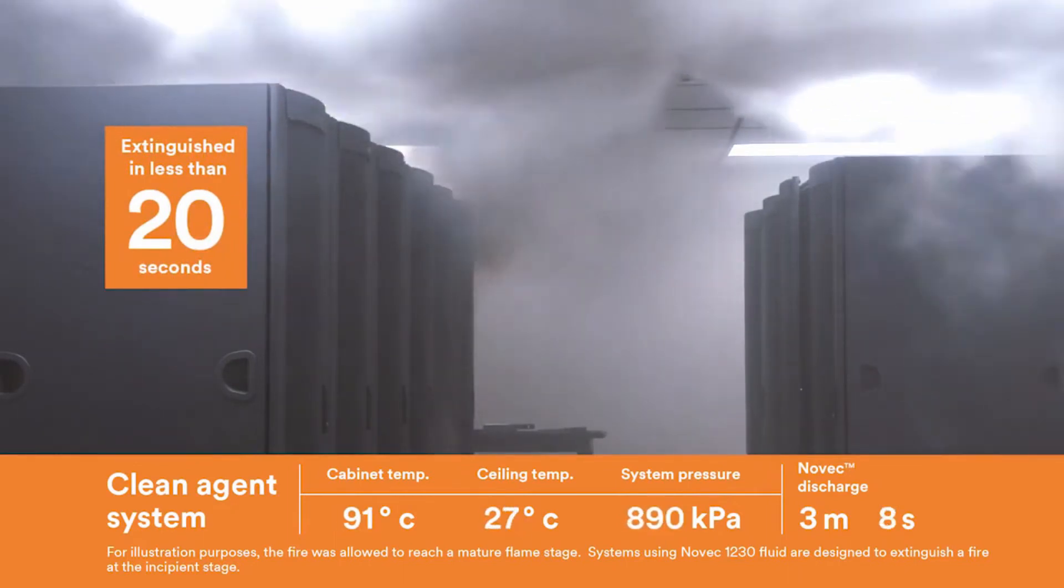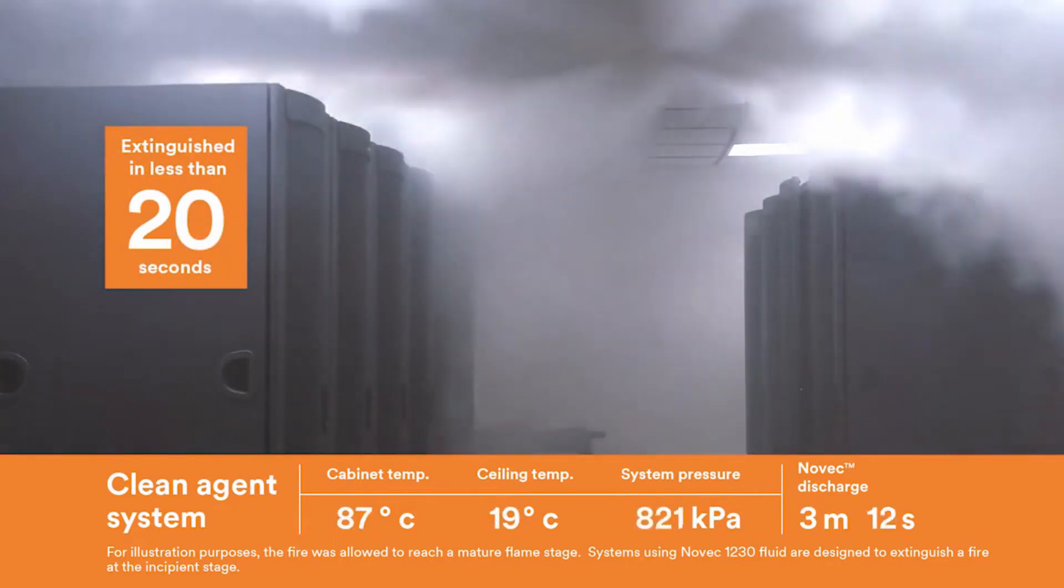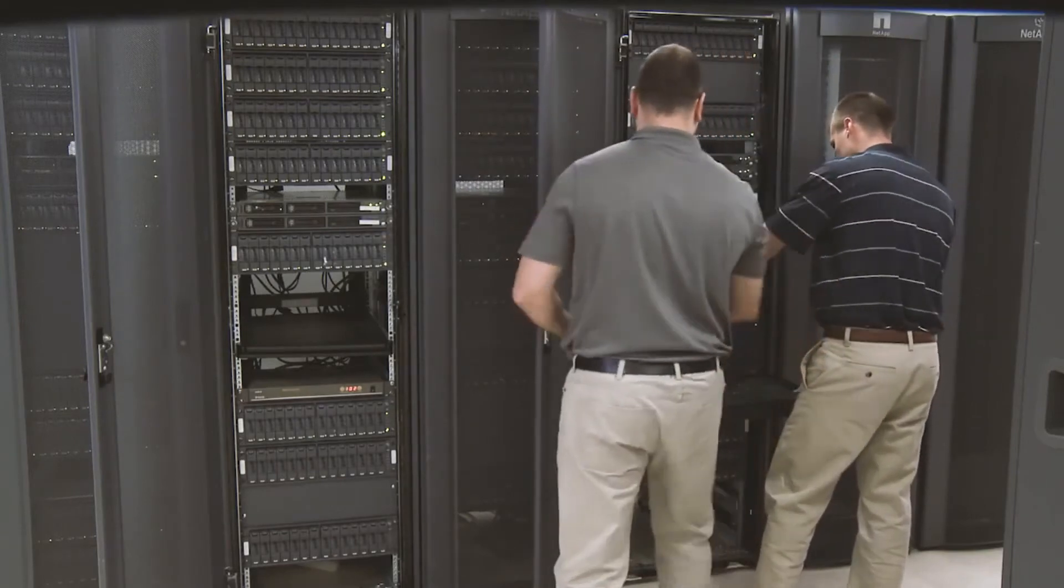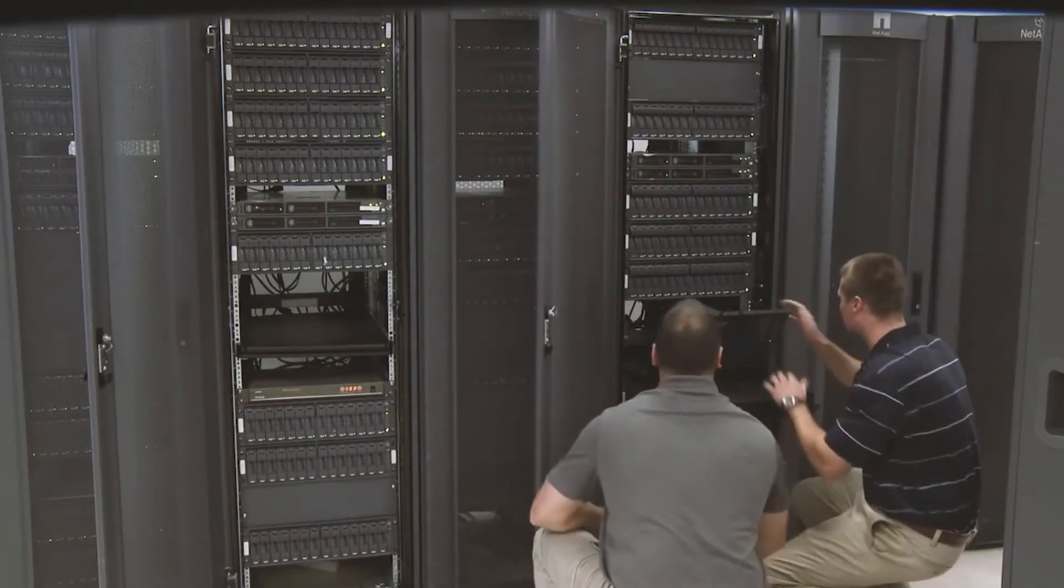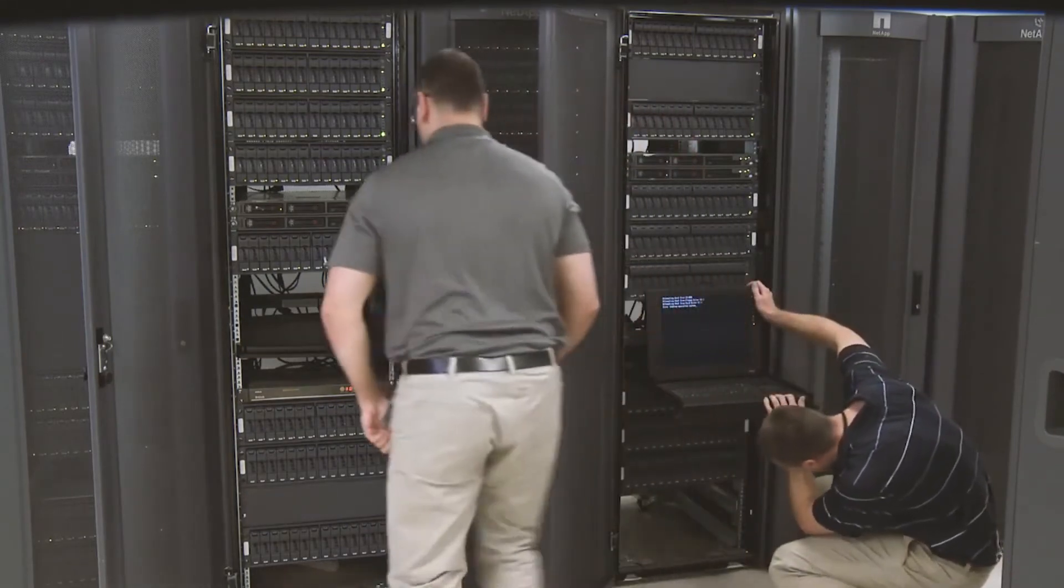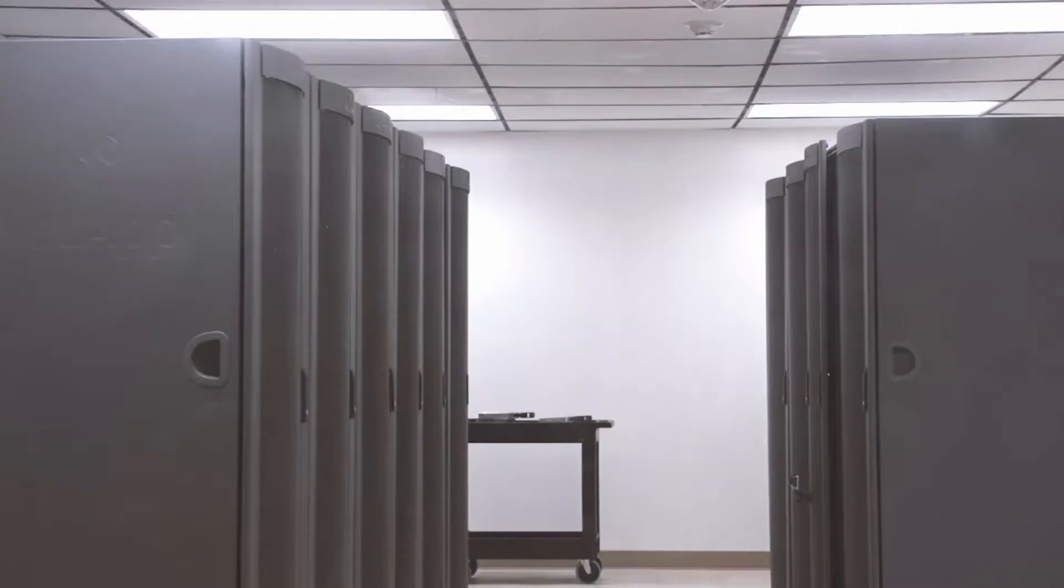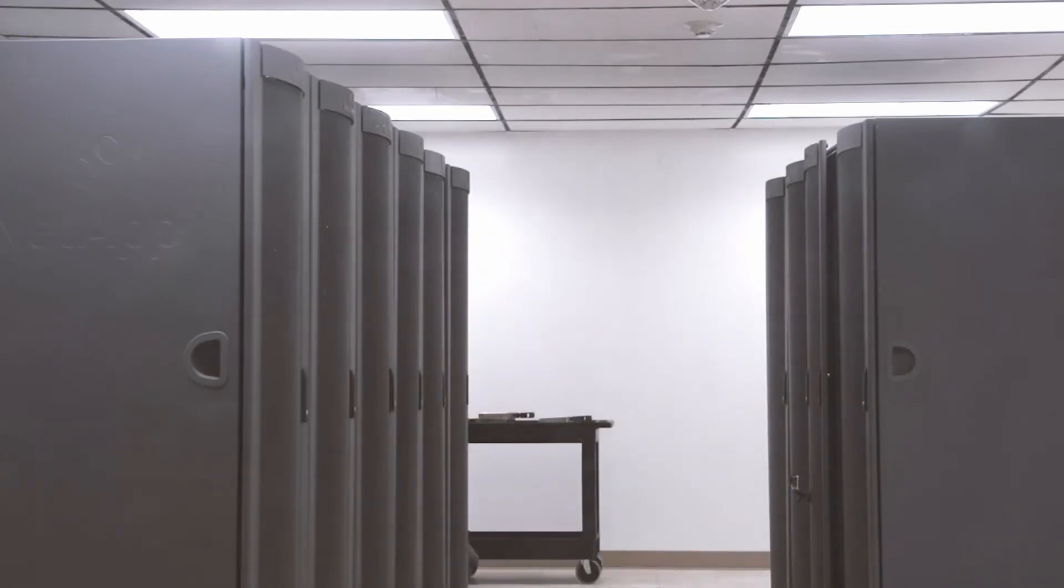A clean agent fire suppression system is designed to detect a fire at an earlier stage, helping to further reduce possible damage. After the smoke and agent have been evacuated, technicians re-enter the chamber to find that the energized servers are still functioning. Equipment and facilities show no signs of damage.